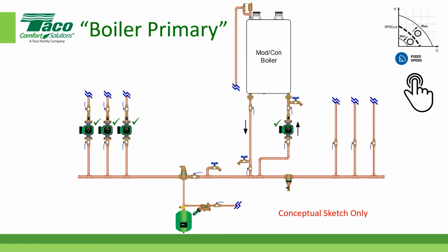So people would say, okay, I'm going to put a pump in there that's 15 gallons a minute. And that's typically what a lot of the boiler manufacturers are going to do as well. And again, I'm telling you a couple things here. Follow what they tell you, but scrutinize what they tell you, because of what I'm going to show you right here. This particular piece of equipment is a condensing piece of equipment. That manufacturer is going to show you that the circulator can be much smaller based on a wider delta T. Let's do that same calculation again. 155,000. I'm putting that in my calculator. I'm going to divide it by a 30-degree delta T, and then I'm going to divide it by 490 again. That says I only need 10.5 gallons a minute.